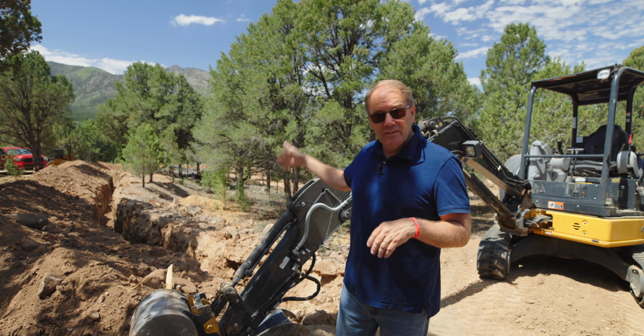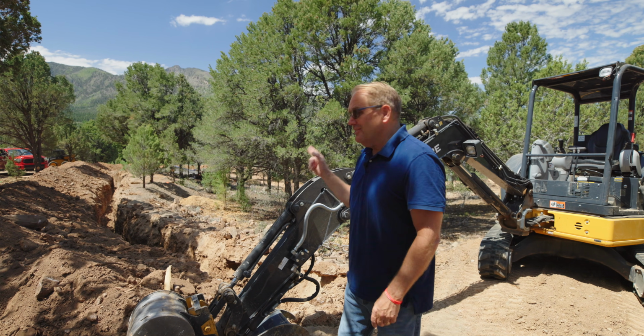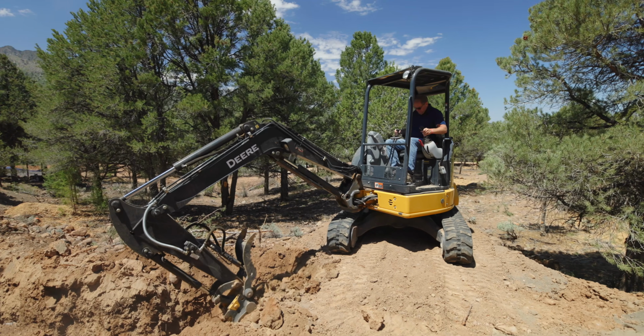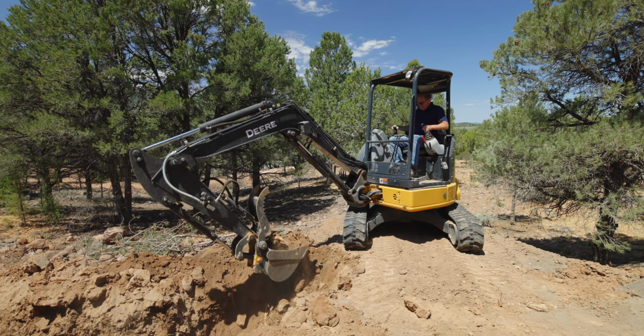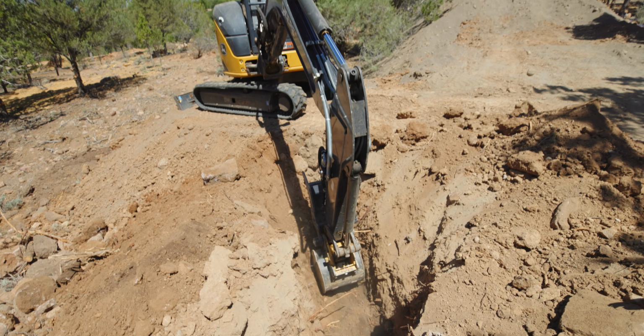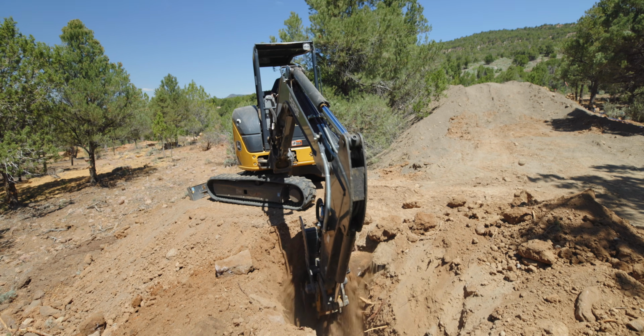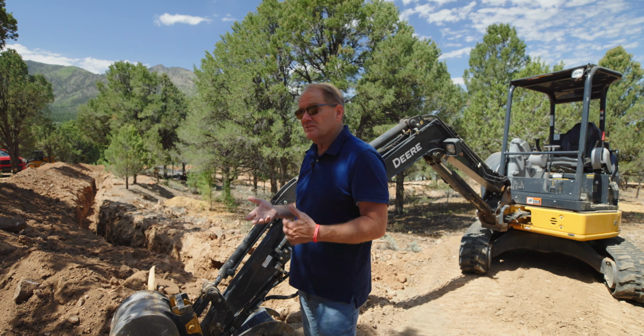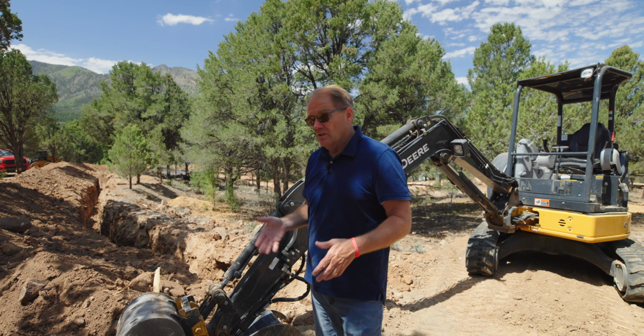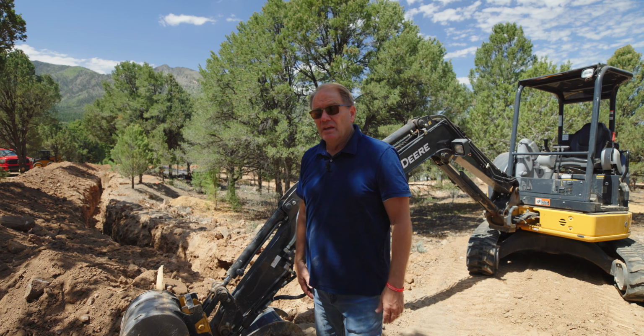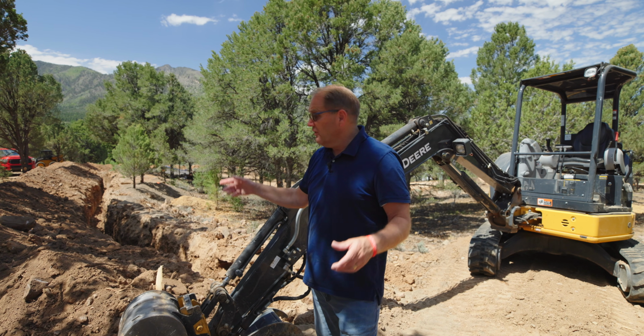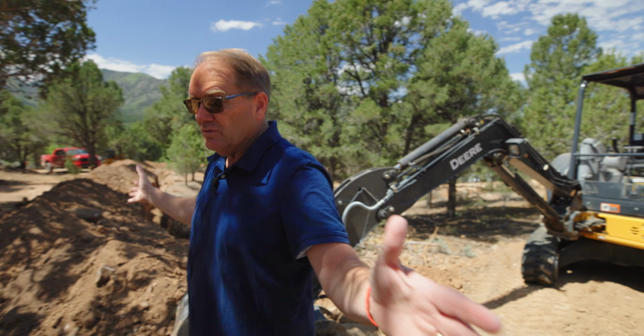So we're going to do that at the same time. Why? Because this trench took almost 3.5 days to dig - it was not easy, very hard pan clay especially near the bottom. You don't want to expend the additional cost of a third trench just for low voltage; that can be very, very costly. And the other thing we did was get water in, which is right about here.